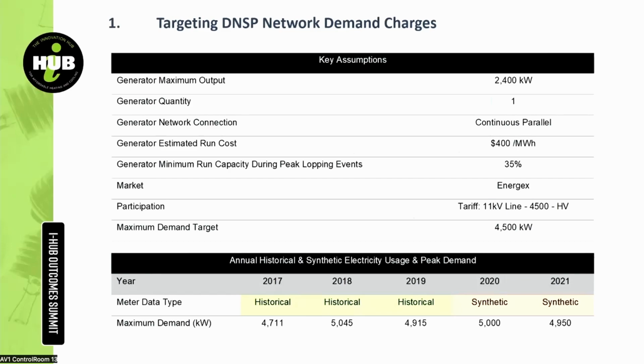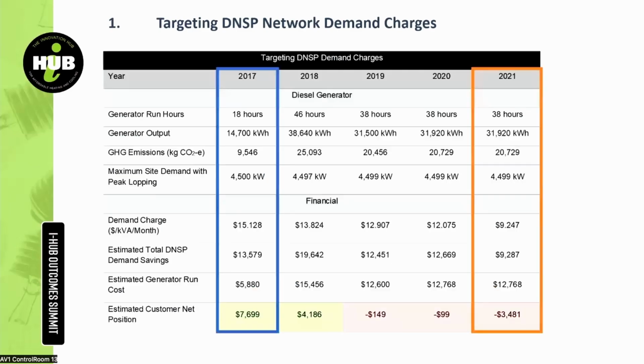And here were the key modelling assumptions shown in this first table here. So the size of the generator, which is 2,400 kilowatts, the generator run cost, the minimum run capacity of the generator to ensure that it's not underloaded. We assumed a network tariff for the site, and we set a maximum demand of 4,500, which would be the point where the generators would turn on to make sure that we don't exceed that. And then in the second table here, we can see the historical maximum demand for this particular site. And you can see that we're trying to reduce the demand by between about 200 kilowatts and 500 kilowatts, depending on the year. Next slide, thanks.